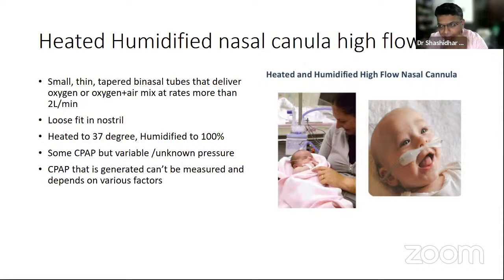So we heat the air to normal body temperature, at least 34 to 37, and we humidify to 100%, ideally 95 to 100% in most devices. And we deliver it through a nasal cannula, which is soft, with small, thin, tapered binasal tubes, and which can deliver oxygen or an oxygen and air mix at flow rates of more than 2 liters per minute.